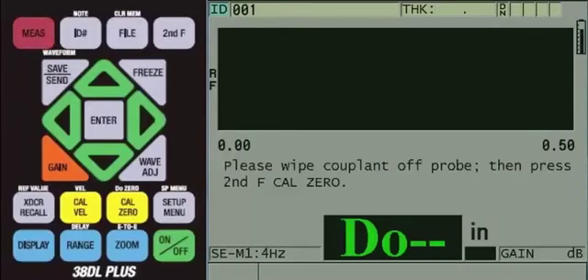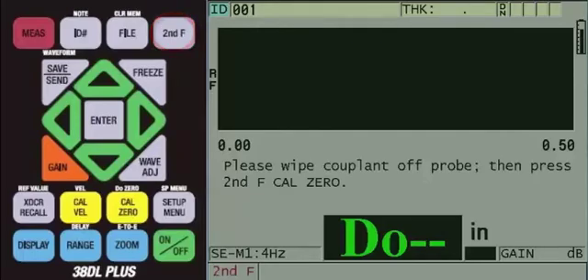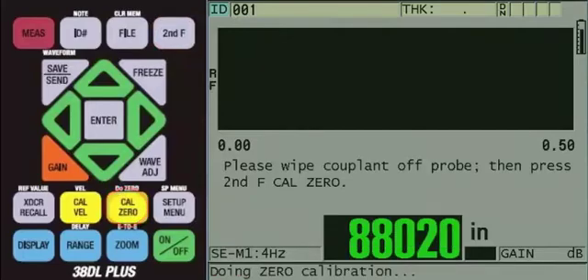Next, because this transducer utilizes a delay line but is used in mode 1, it is required that you perform a DO-0. To do this, wipe any couplant off the face of the transducer, then press and release the second F key first, then press the yellow CAL-0 key. This allows the gauge to compensate for the time through the delay line.